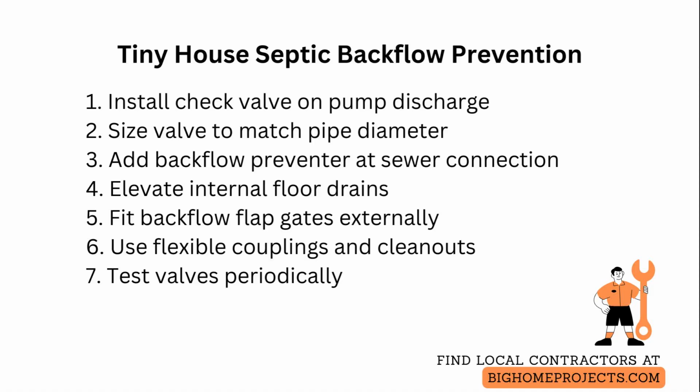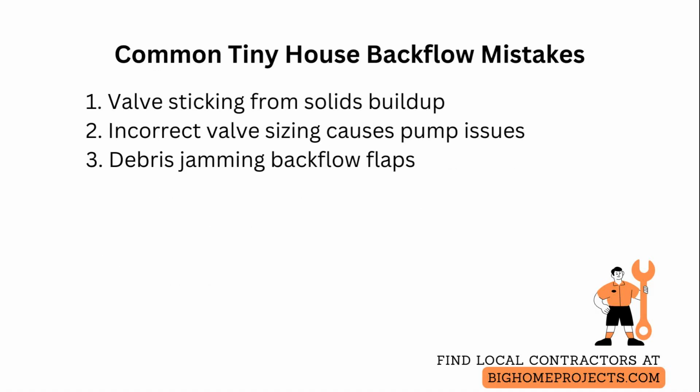Test all valves and check devices periodically by simulating back pressure with a controlled water source or following manufacturer test procedures, and replace any unit that leaks, hums, or shows delayed closing. Common issues include valve sticking from solids and grease buildup, which you can prevent by installing accessible cleanouts and scheduling routine flushing with biodegradable enzyme cleaners to break down residues, plus remove and service the valve if sticking recurs.